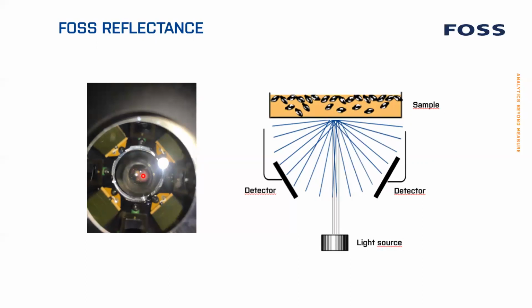So you have the light coming in here in the middle, and then you have detectors, and there's actually 8 detectors, 4 of them being silicon detectors and 4 of them being lead sulfide detectors. And for the type of sample we have, it's really important that you have a big area to collect the light from, because if the sample is not very homogeneous, and in most cases it's not, it's important that the detector area is big, so you get as many different types of light coming back to the detectors as possible, to give a true representation of the sample.